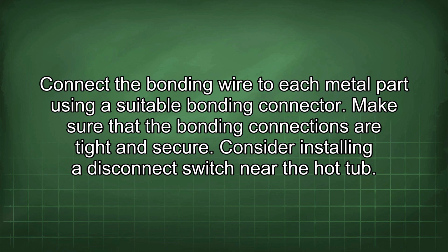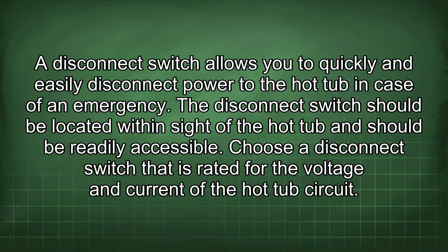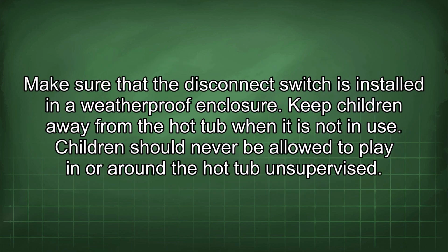Consider installing a disconnect switch near the hot tub. A disconnect switch allows you to quickly and easily disconnect power to the hot tub in case of an emergency. The disconnect switch should be located within sight of the hot tub and should be readily accessible. Choose a disconnect switch that is rated for the voltage and current of the hot tub circuit. Make sure that the disconnect switch is installed in a weatherproof enclosure.